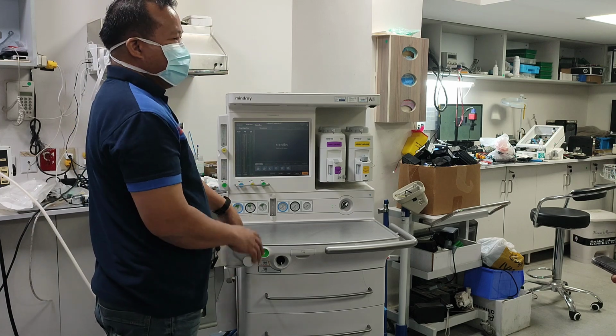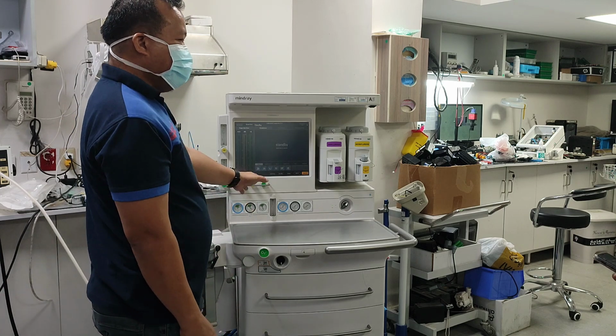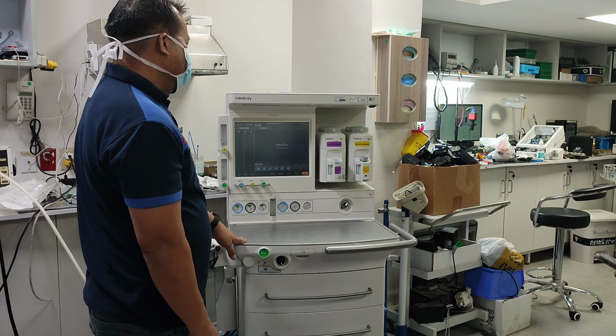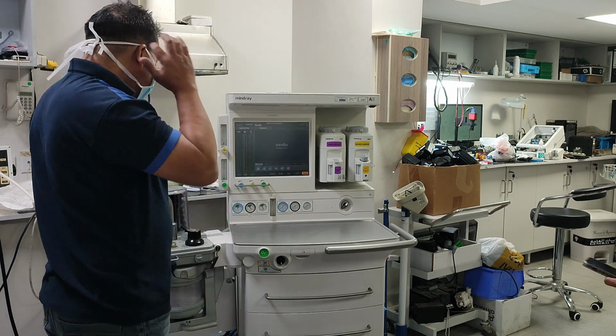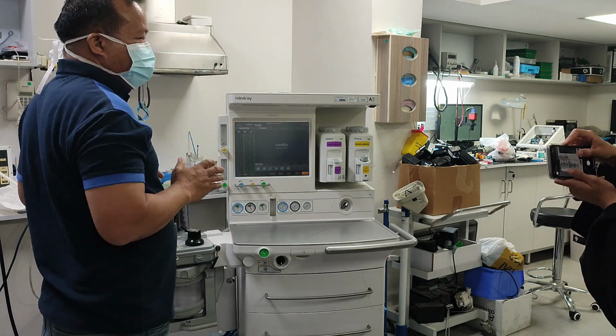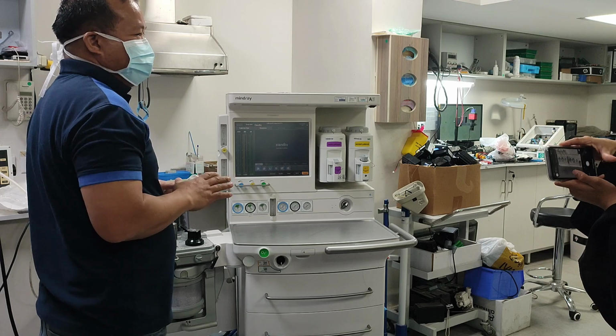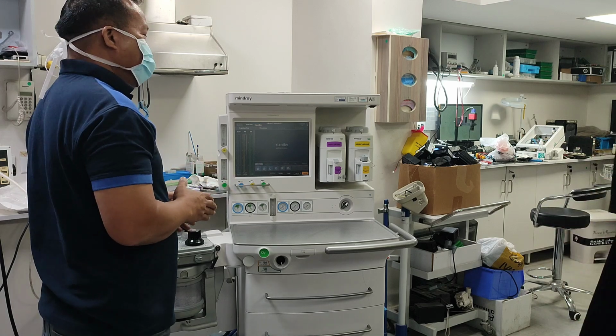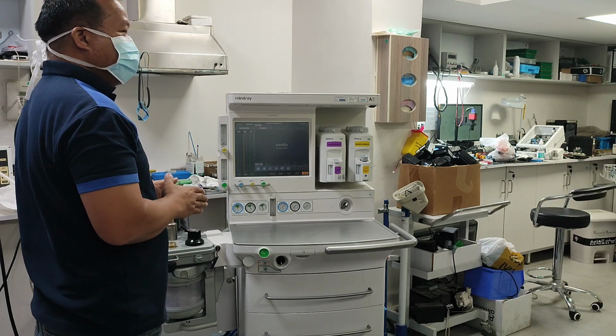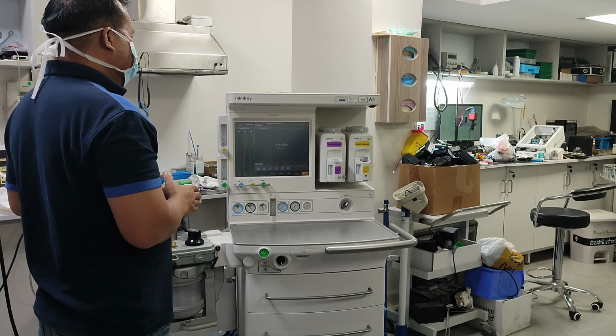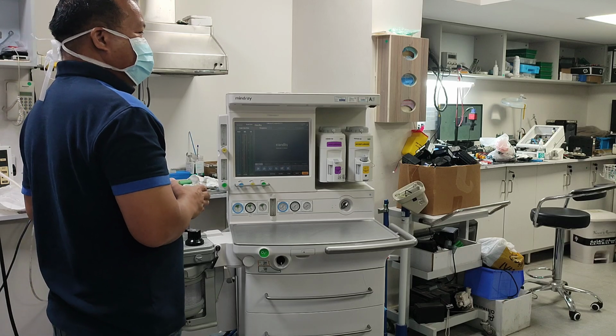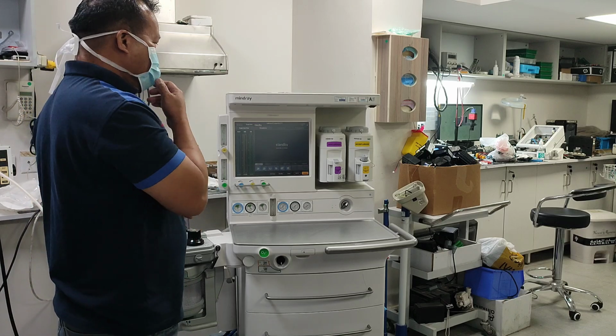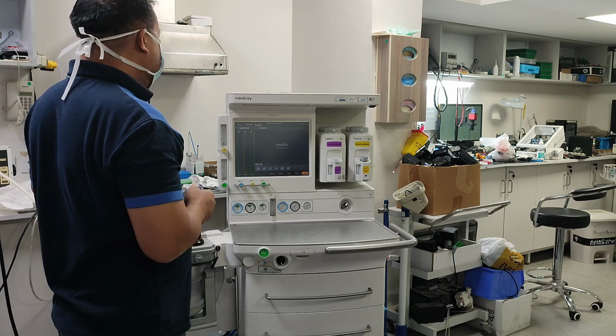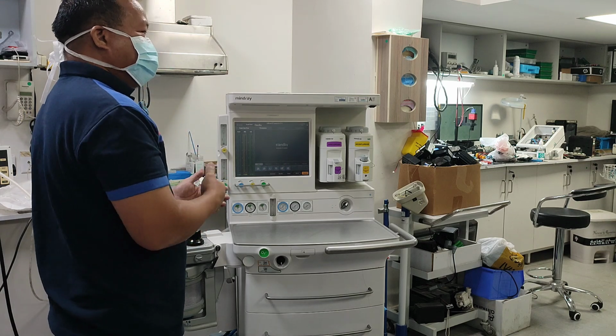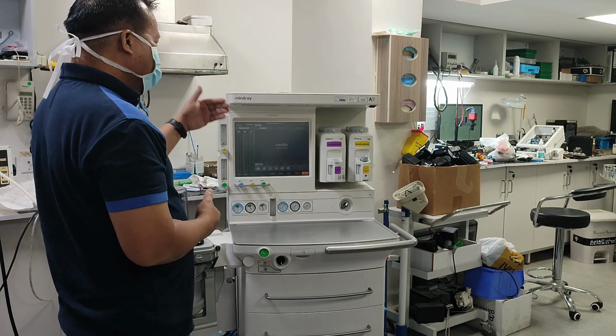All anesthesia machines are like this. There is always a backup of oxygen, air and nitrous at the back, so the operation will not be interrupted. It will continue because operation is very dangerous and a very complicated situation. If something happens with the gases, there is a backup. That backup is at the back.